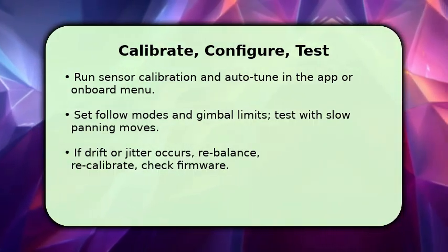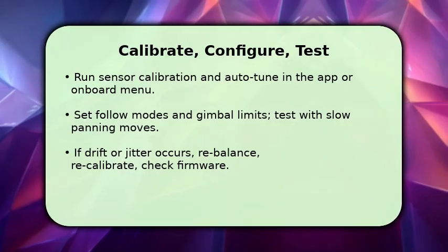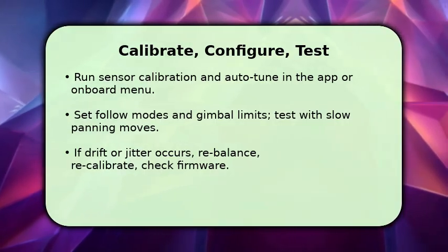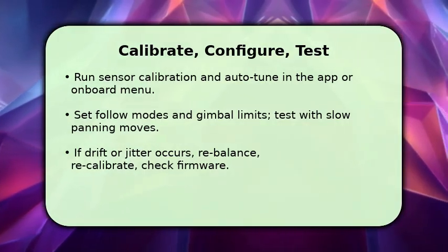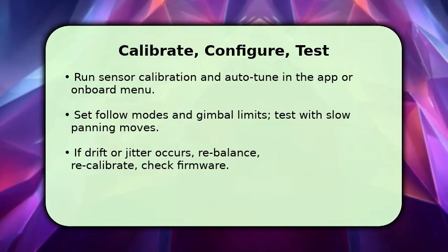If you see drift or jitter, rebalance and run calibration again, check for loose screws, and update the firmware. These troubleshooting steps fix most persistent issues quickly.